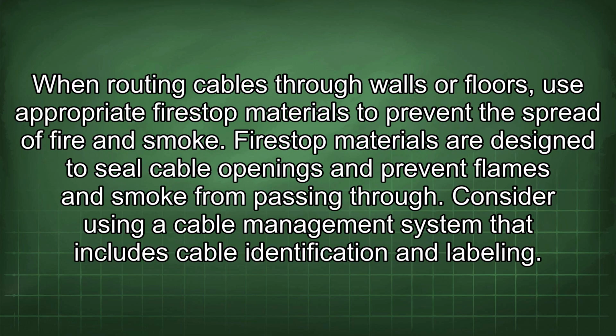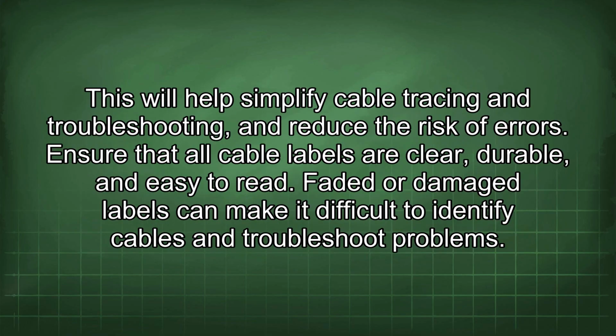When routing cables through walls or floors, use appropriate fire-stop materials to prevent the spread of fire and smoke. Fire-stop materials are designed to seal cable openings and prevent flames and smoke from passing through. Consider using a cable management system that includes cable identification and labeling. This will help simplify cable tracing and troubleshooting and reduce the risk of errors.